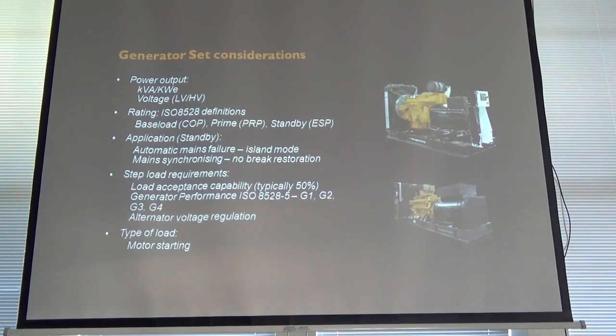The reason why you've got either or on this, again, it's capping the limits on the stress, and because you're running this on a limited basis, average variable load, it's derating it, keeping it within stress limits. So that probably covers that nicely. Application itself, it might be automatic mains failure, you might have a set running in island mode, you might have multiple sets synchronizing and paralleling with the grid for a short-term or long-term basis. So there are very much different applications and requirements that you want for the unit.